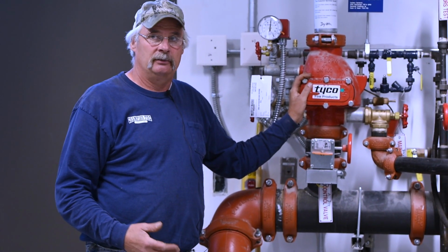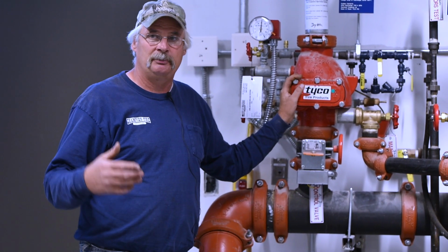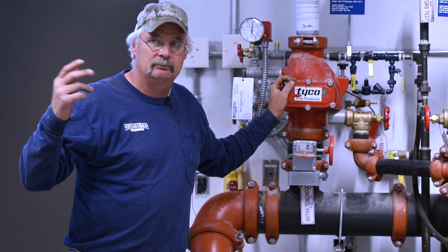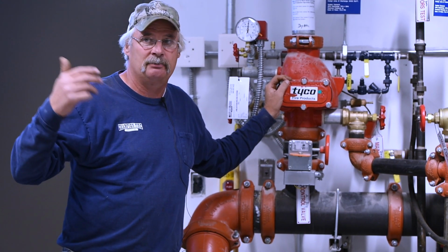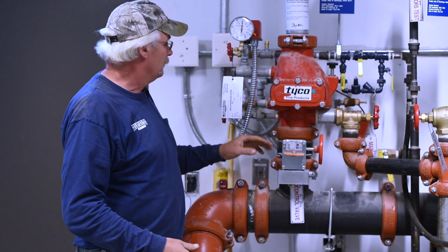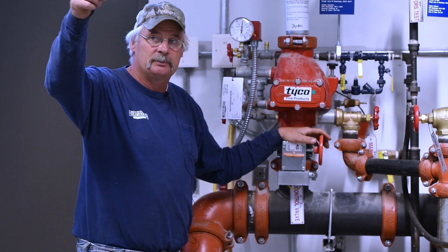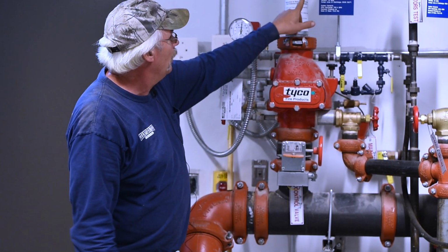Dry system. Got a problem in the attic. Somebody's up there crawling around, pulling wires, broke a line, trap pipe, whatever, froze something up on us. Shut it off. Open the drain, open the inspector's test drain, call immediately.